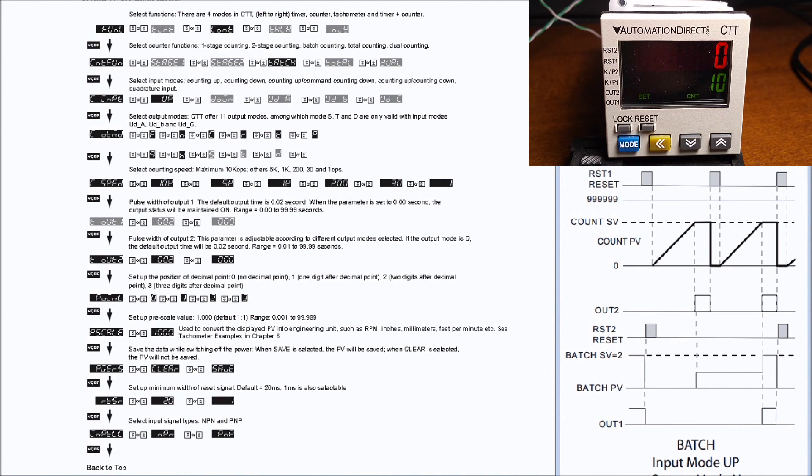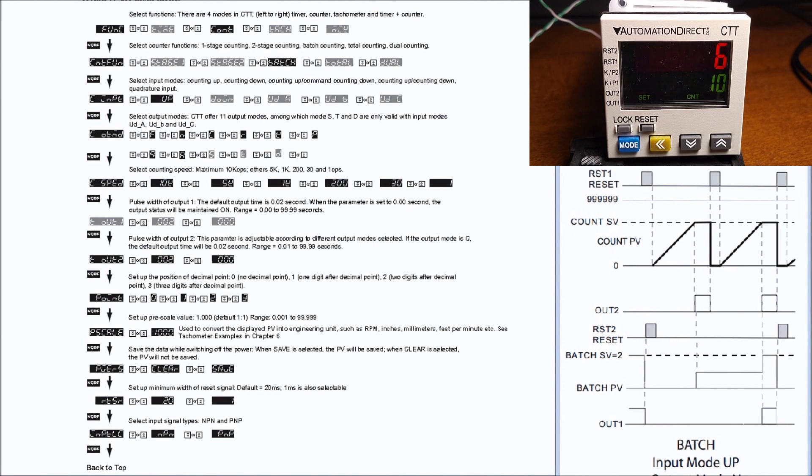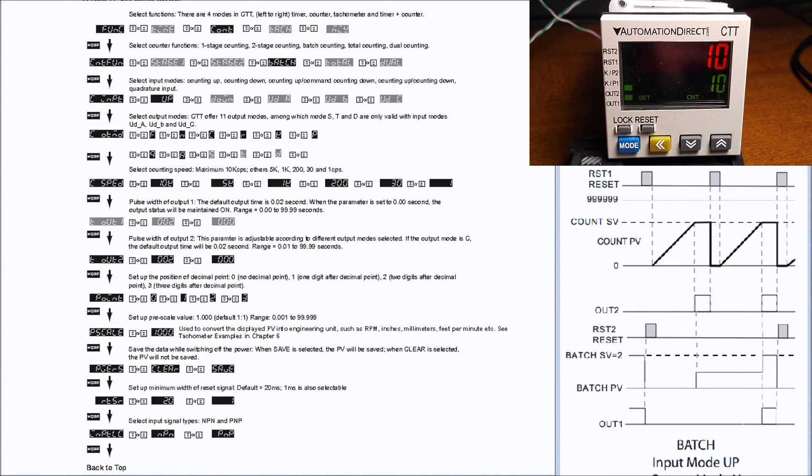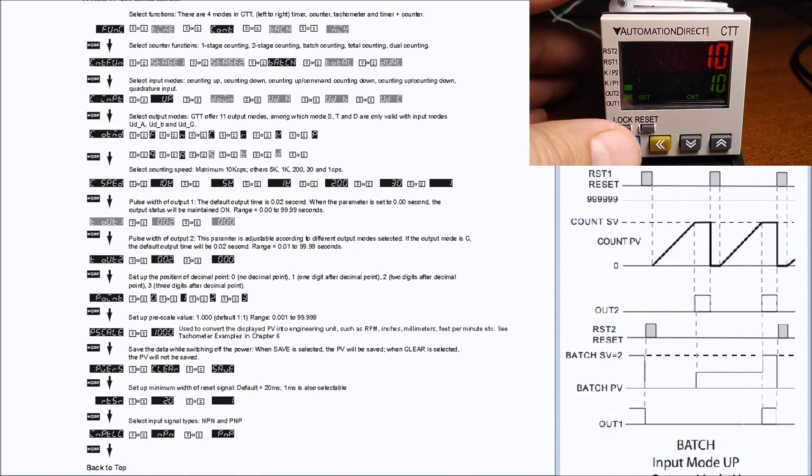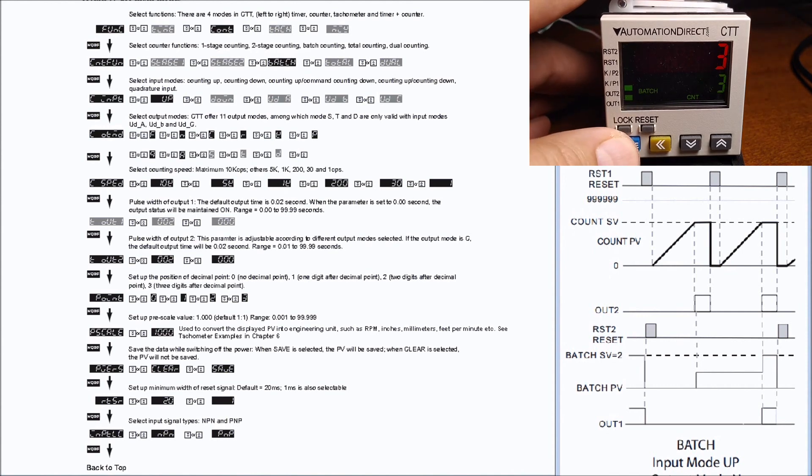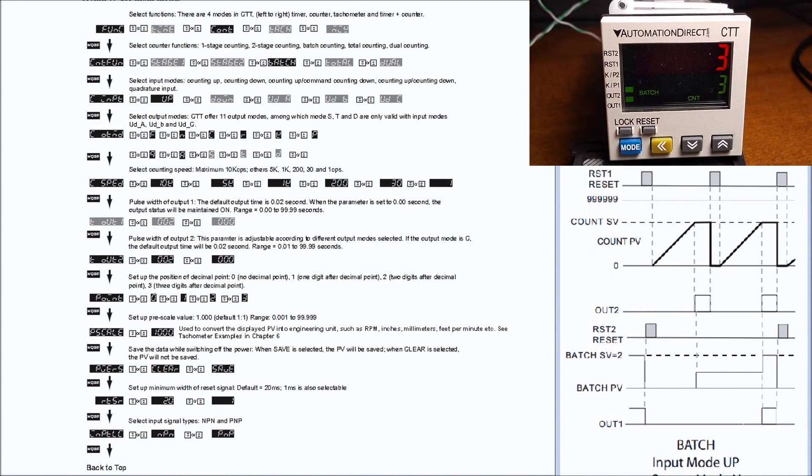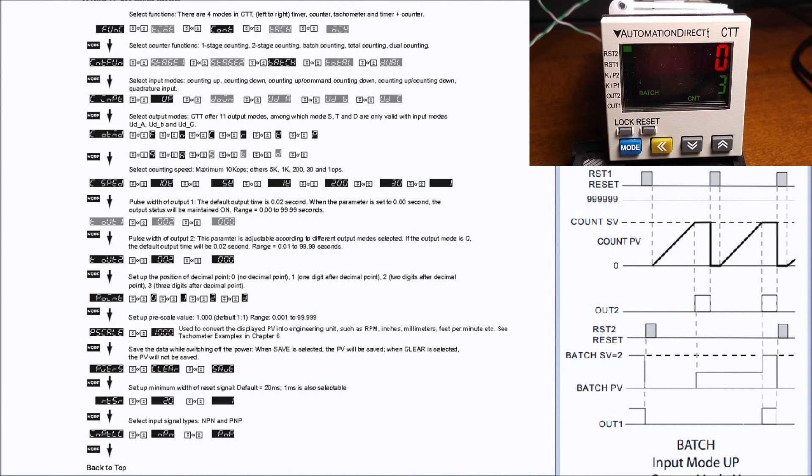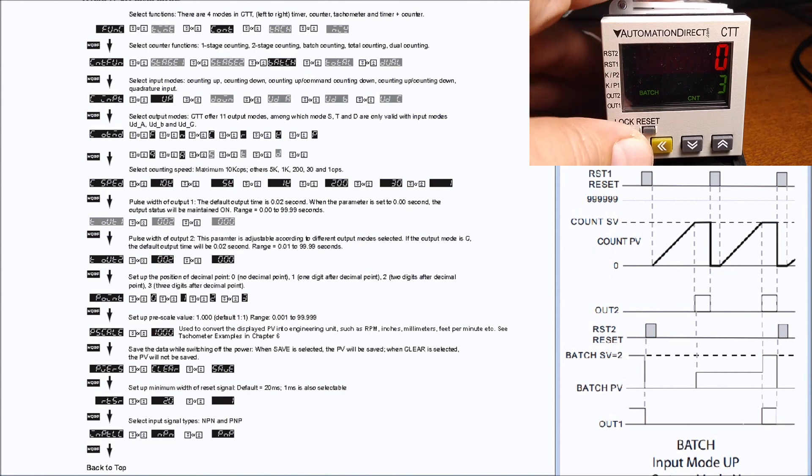We'll send some more pulses. Now when we hit the value of 10 we have both outputs on now, and that is simply because now our batch has been set or determined. We have a present value of three and a maintained value of three, so both outputs are now on. In order to reset that we use our reset inputs, first of all for the actual count and then our second reset for our batch, and everything starts again at zero.